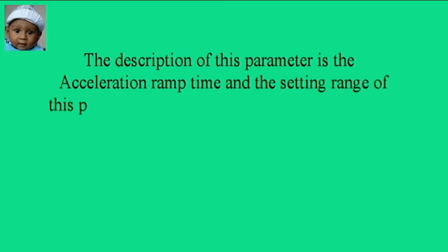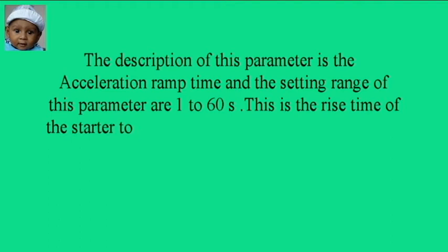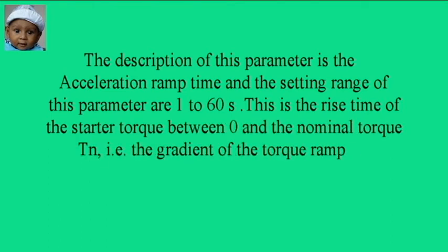Another parameter is ACC, acceleration ramp time, and the setting range of this parameter is 1 to 60 seconds. The default value is 15 seconds. I have also tried to explain the acceleration ramp time with the graph.